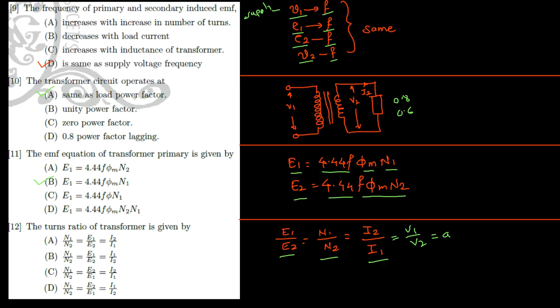Let me launch the next question. The laminated core of the transformer is made up of material chosen because there are two losses in the transformer: hysteresis loss and eddy current loss. So iron losses in the transformer equal hysteresis loss plus eddy current loss. Hysteresis loss can be minimized by using high graded steel with low hysteresis. Looking at the hysteresis characteristics, the area under the BH curve represents the hysteresis loss, and this area will be very small for silicon steel.